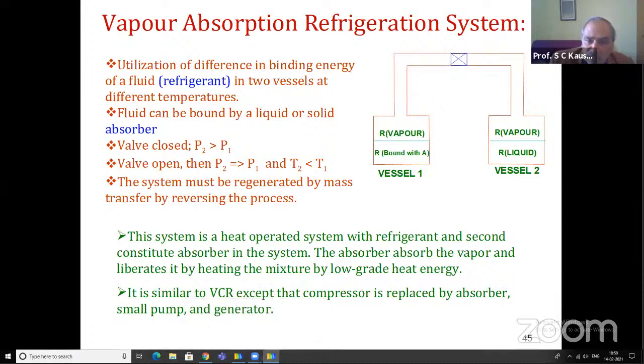Now, in a vapor absorption system, the refrigerant vapor coming from the evaporator is dissolved in some absorbent solution so that it is converted into liquid phase. As you can see here, the combination of refrigerant and absorbent is heated with the help of the input energy, say solar energy, and then the refrigerant vapor goes out and is condensed in vessel 2. So based on vessel 1 and vessel 2, the basic vapor absorption process can be understood.